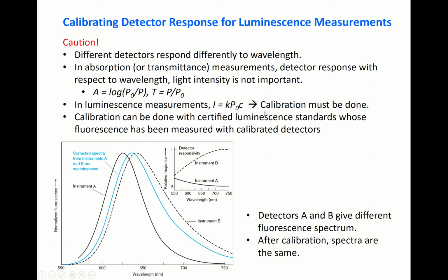Calibration must be done, otherwise you will get a distorted spectrum. Calibration can be done with certified luminescence standards whose fluorescence has been measured with calibrated detectors.